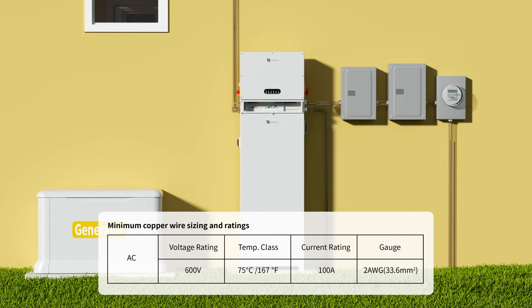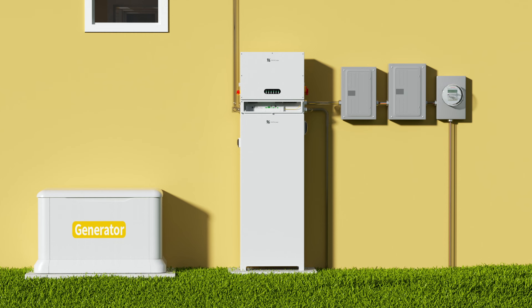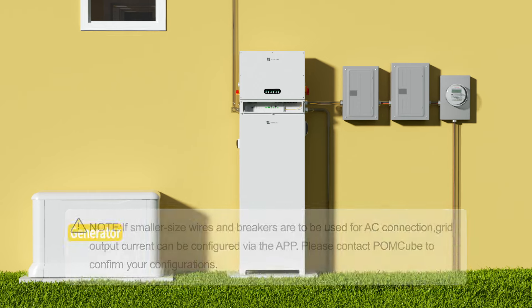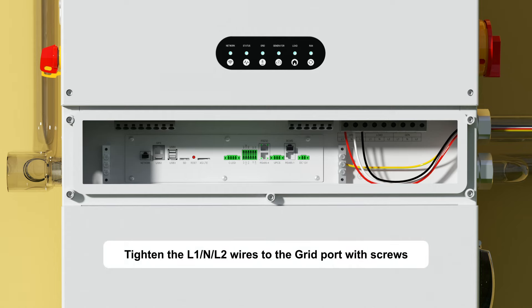Minimum copper wire size and ratings. Note: if smaller size wires and breakers are to be used for AC connection, grid output current can be configured via the app — please contact POMCube to confirm your configurations. Tighten the L1, N, and L2 wires to the grid port with screws.